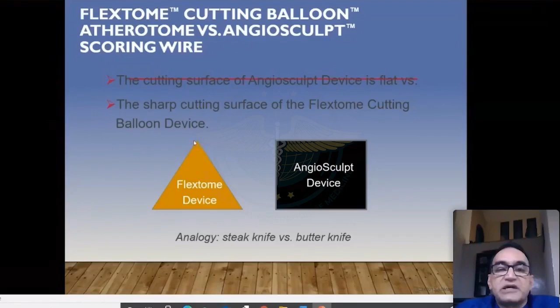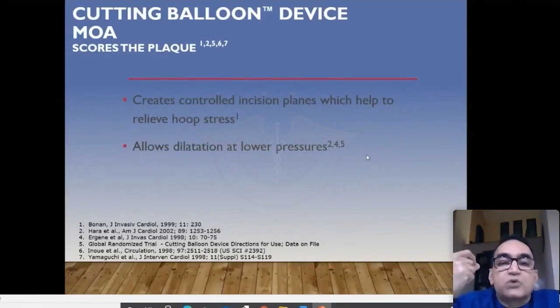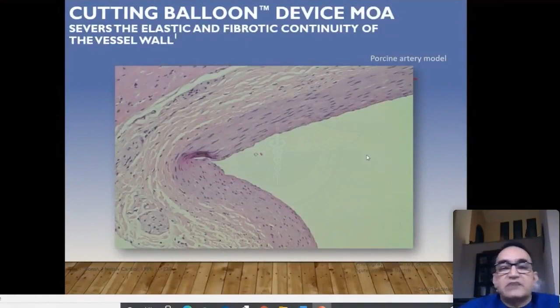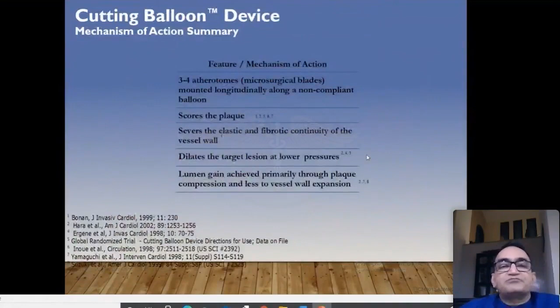Cutting balloon device scores the plaque, creates controlled incision planes which help to relieve the hoop stress. What is hoop stress? The stress that is there on the surface of the atheroma. It's not easy to explain in a short time, but basically there is a certain stress created on the atheroma surface, and merely dilating it with a balloon may not help. You may have to give a cut. By giving it a cut, it will actually reduce the need to go to higher pressures. So it allows dilatation at lower pressures. That's an important point. So you can see here a cutting balloon device that has severed the elastic and fibrotic continuity of the vessel wall and has given a neat cut, and therefore it allows the balloon to expand at a lower pressure and open the vessel.